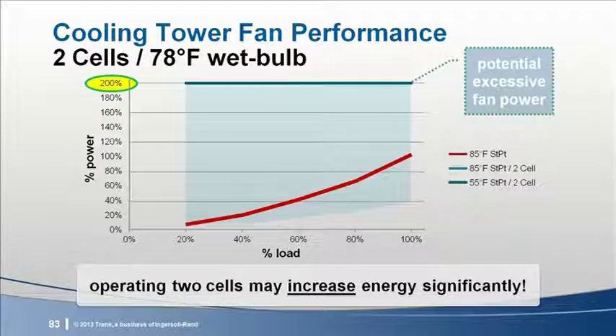While this would provide somewhat cooler supply condenser water, the resulting power saving from the chiller could not come close to offsetting the excess power consumed by the tower fans. This is one of the key risks of adding a VFD to a component. It may save energy, but it may result in significant energy loss as well. Let's move on and look at the sequencing of chillers with variable speed drives. It will turn out to be a little more interesting.